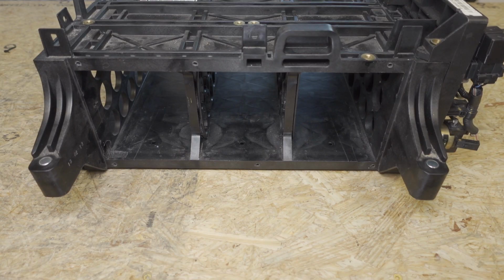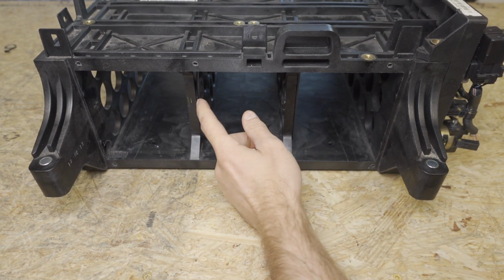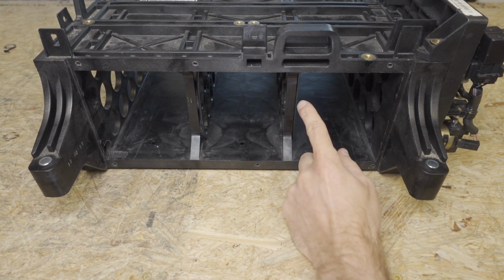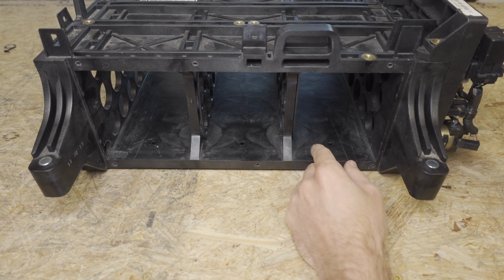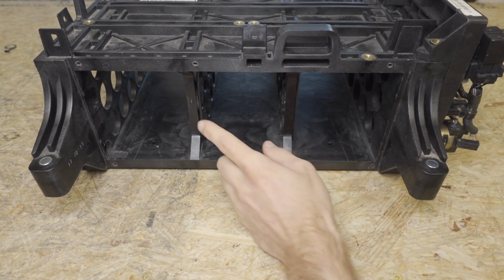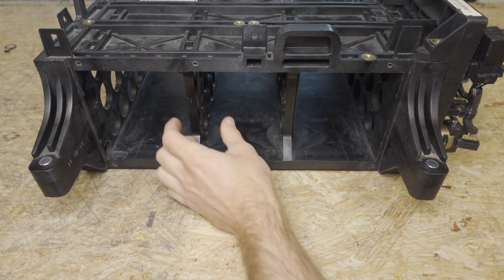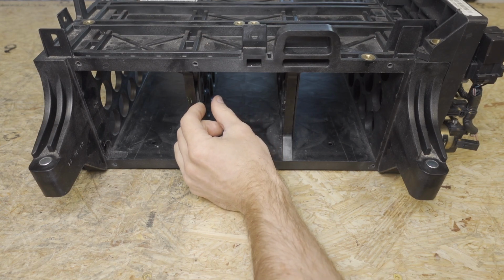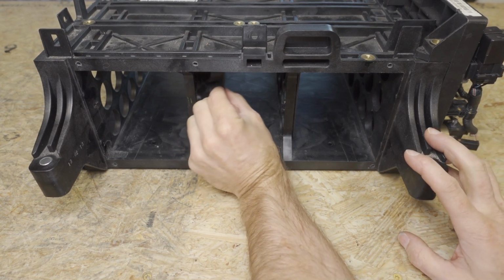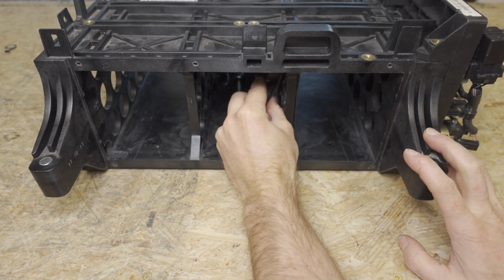Before we install the battery modules, we need to modify one of these rubber gaskets. The gasket that's closer to the junction board, we can leave the same, but the one between the two 18S modules, we need to modify. This is a safety issue, and you must do this if you are using the gaskets.